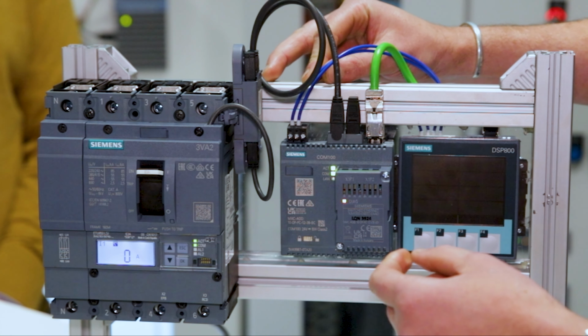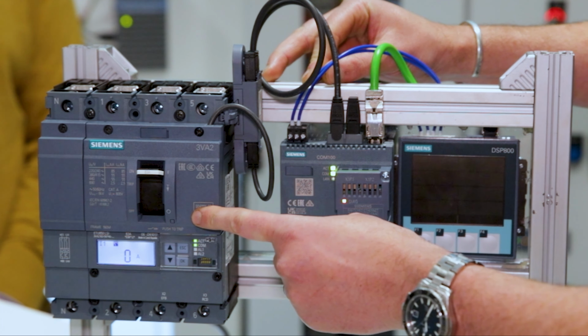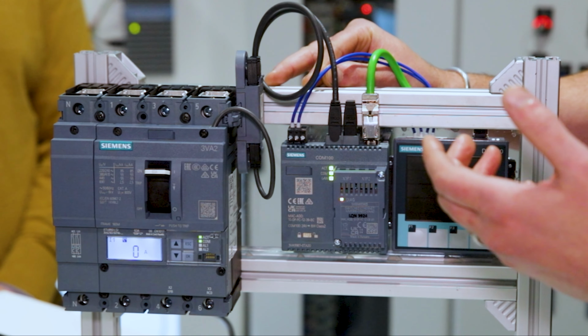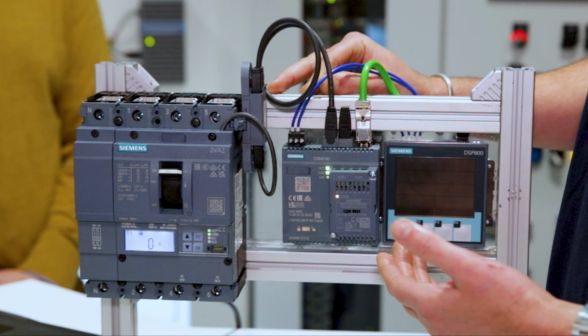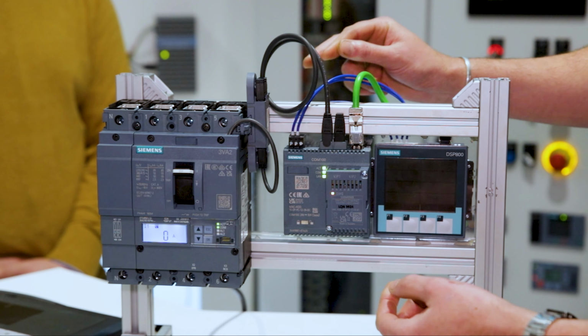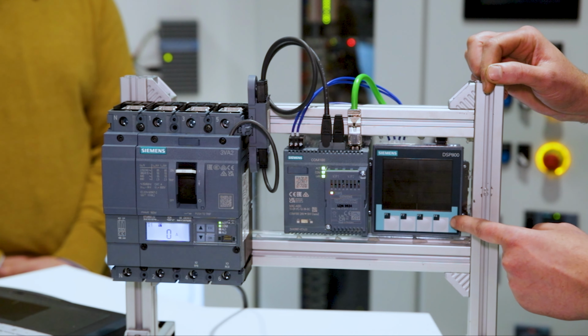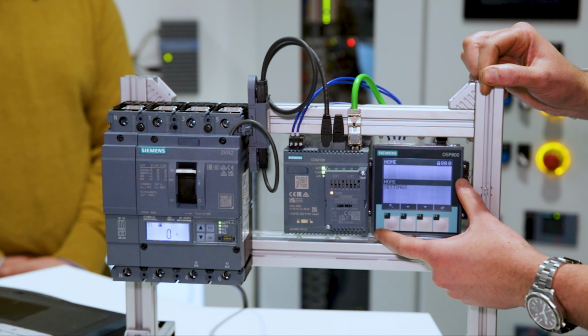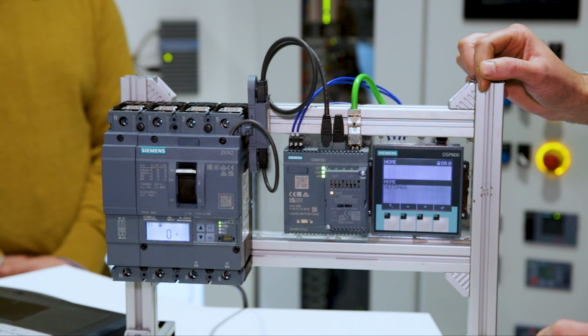The way that we communicate with this to a higher level is inside here we've got a COM60. So it goes through the T connector into a COM100. Now there's two of these devices. There's a COM100, which means we can have one breaker, or there's a COM800, which means we can use up to 8 breakers. On the front of the COM100, we have an expansion module, so this is a Profinet version. The Profinet one we would typically connect to a switch or building management system or a PLC. You can also use Profibus or Modbus. On this COM100, we've also got connected a DSP800, and this allows us to then display on the panel front what is displayed on the ETU.